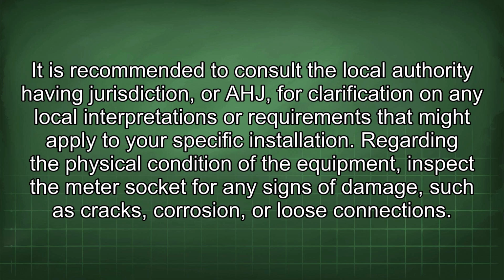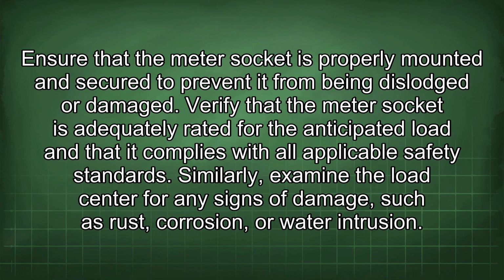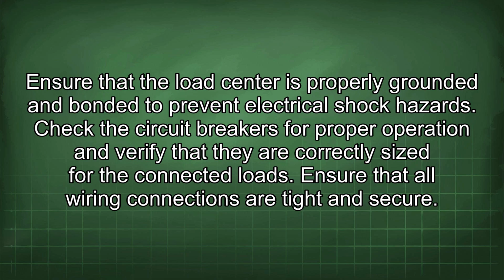Regarding the physical condition of the equipment, inspect the meter socket for any signs of damage such as cracks, corrosion, or loose connections. Ensure that the meter socket is properly mounted and secured to prevent it from being dislodged or damaged. Verify that the meter socket is adequately rated for the anticipated load and that it complies with all applicable safety standards. Similarly, examine the load center for any signs of damage such as rust, corrosion, or water intrusion. Ensure that the load center is properly grounded and bonded to prevent electrical shock hazards. Check the circuit breakers for proper operation and verify that they are correctly sized for the connected loads. Ensure that all wiring connections are tight and secure.